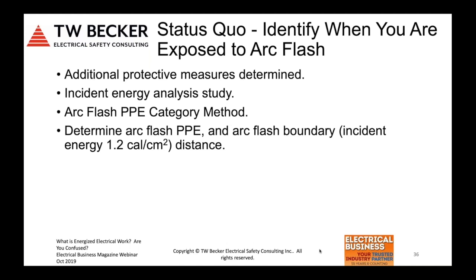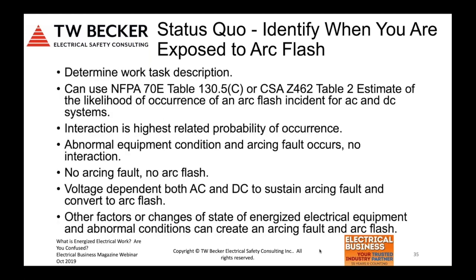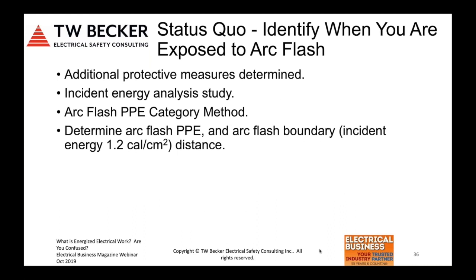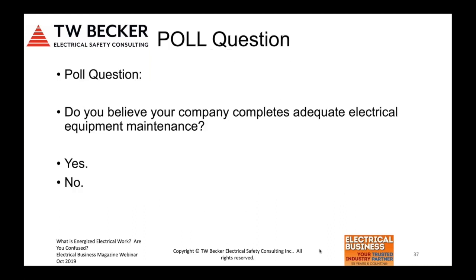So again, arc flash risk assessment is a process, 3 steps. Again, we can use table 2 or Table 130.5(C) for NFPA 70E in that process with the work task list that's there. Again, risk assessment is a 3-step process.